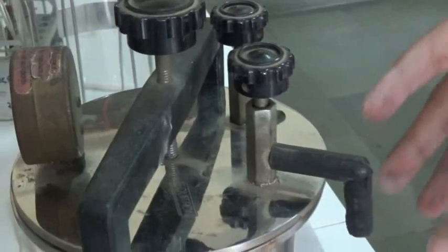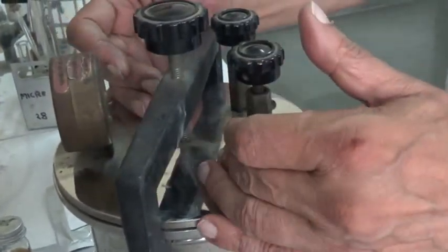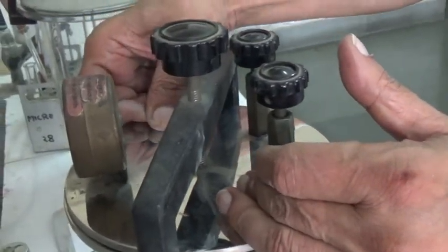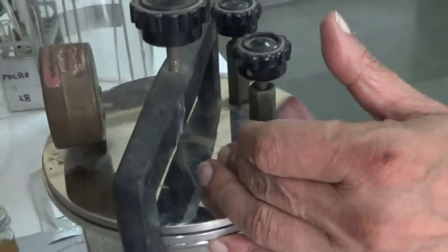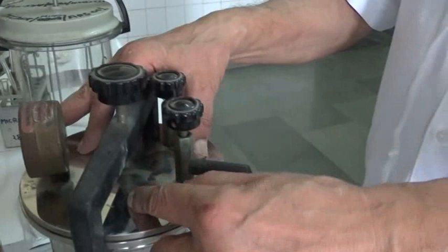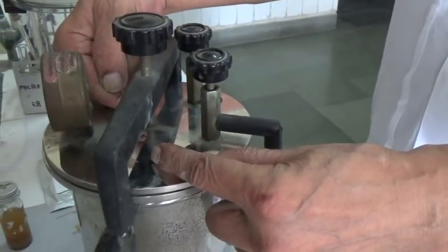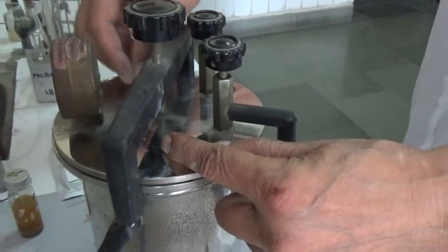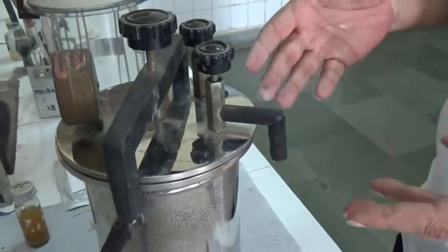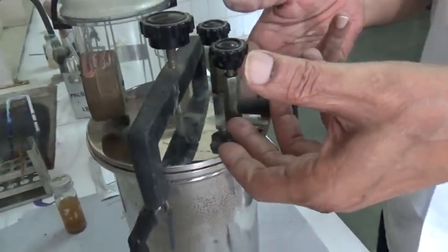We keep it like this for about 20 to 30 minutes, so that when the reaction is taking place inside, the hydrogen and whatever remaining oxygen is there after the vacuum, there is some amount of oxygen still left, that leftover oxygen and the hydrogen will combine in the presence of the catalyst palladium, which is there underneath this lid, and water will be formed. So some amount of hydrogen will be consumed like this, and whatever is consumed, the bladder refills.